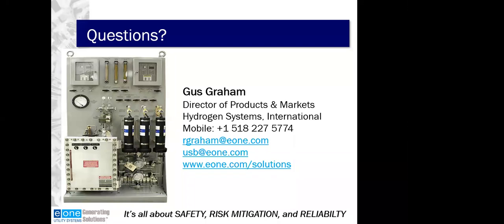Okay, we have a couple questions from actually the same individual. What is the standard voltage we should get during calibration? Okay, good question. And that varies based on the gas that's being calibrated. So it's probably best, I don't want to repeat incorrectly the information that's going to be provided by our great lead service technician. Chad will be reviewing that during the video, and he'll walk through what the standard ranges are expected on each of those voltages as you apply those gases. During normal operation, the sample voltage should be between 3.5 and 4.0.